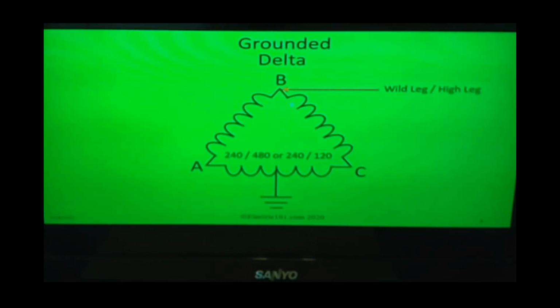So because of the higher voltage on either one of these, the code requirements or building codes require this circuit right there to be orange. There's not too many places inside of the code books that call for colors. Ground wires are green, with yellow stripes, or bare. Neutral wires are white or gray. And the high leg has got to be orange. Other than that, all the other colors could be used, well, at your discretion.